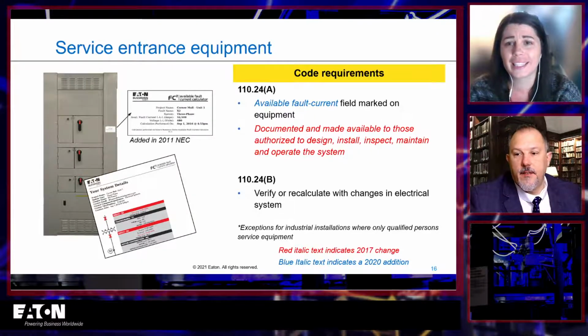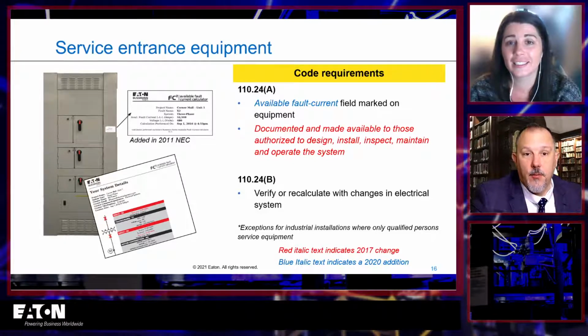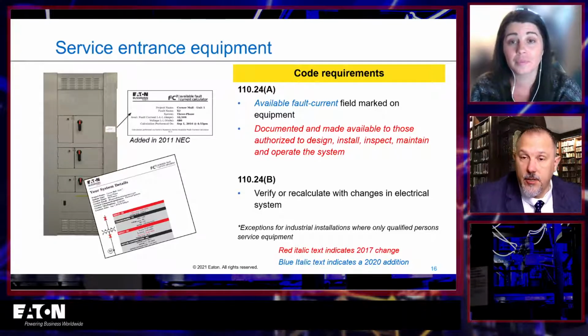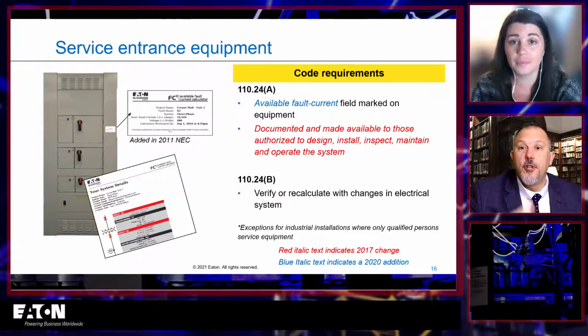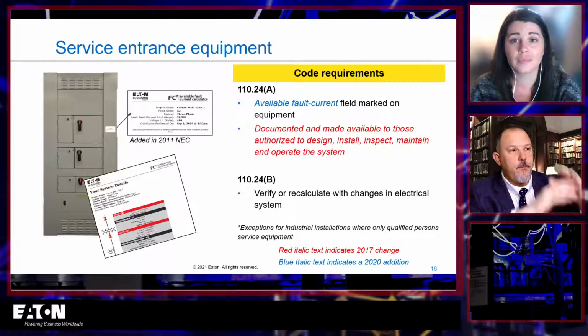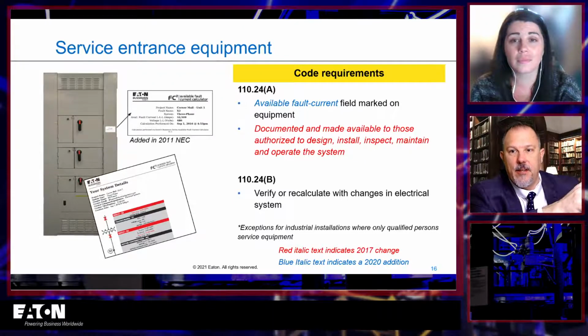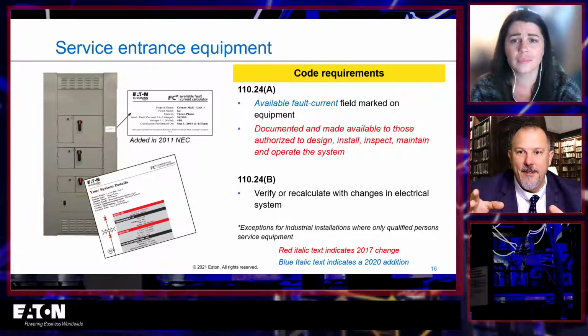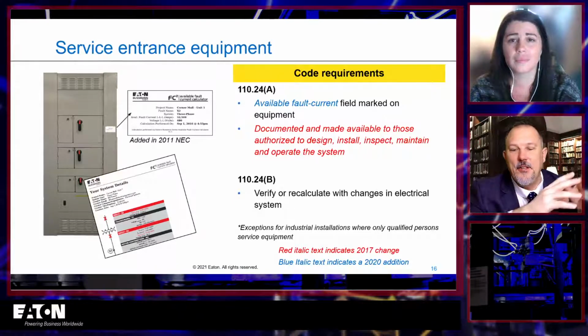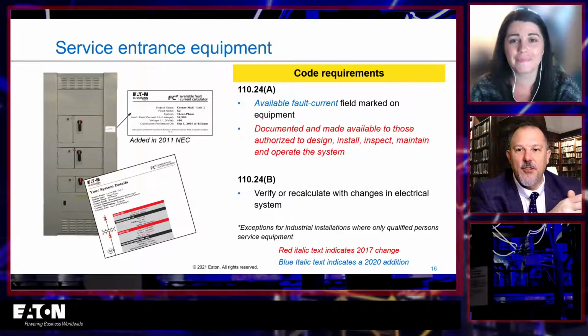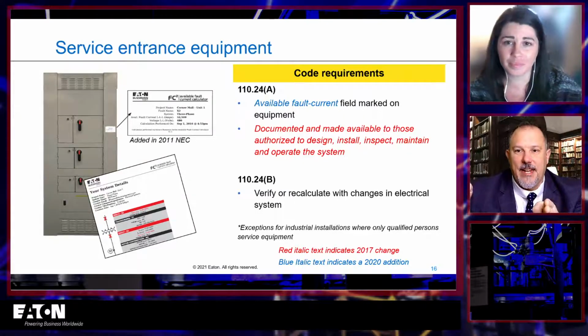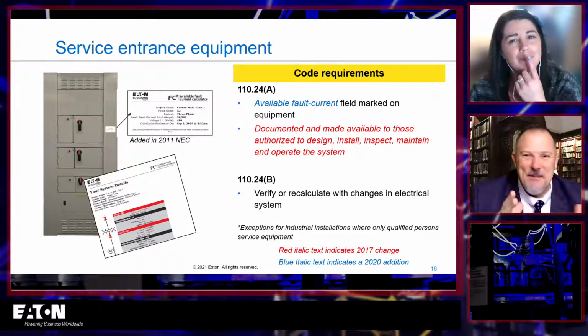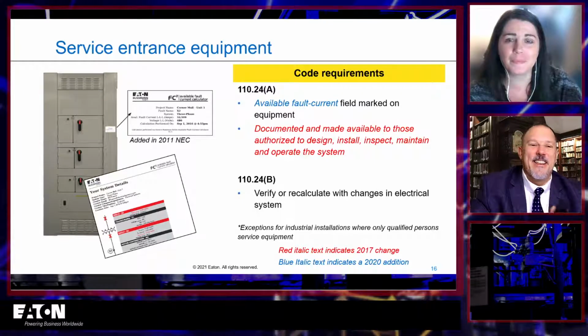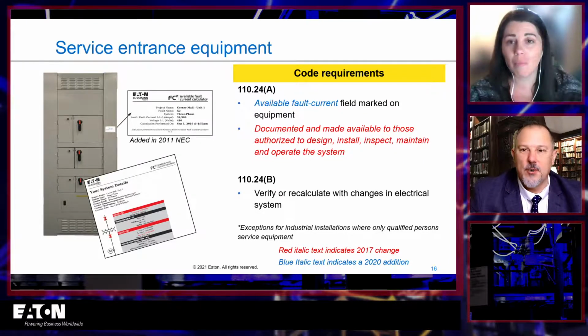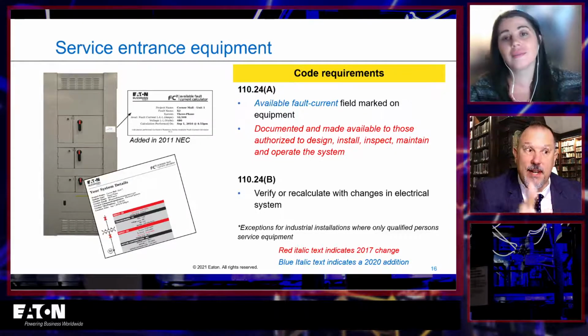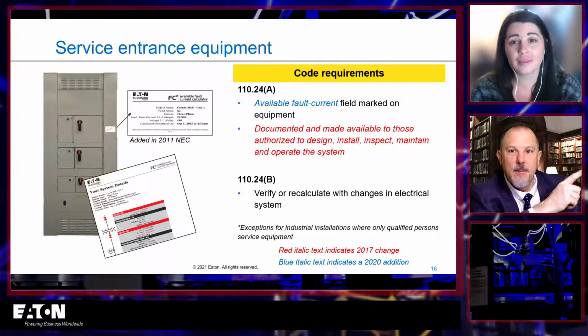Yeah, Christy, and I'll give you some insight on why they required that documentation. I know Donnie Cook and a few other electrical inspectors would show up on a job site and see the available fault current at a panel, and there would be a very short run of conductor. Say there's 60,000 amps at this panel, and there's 10 feet of conductor, and they said there's only 8,000 amps at the next panel, and they would go, something doesn't smell right. Then they would take that FC squared app and run a short calculation, and go back to the contractor and say, look, I believe that number, but I don't believe this number.